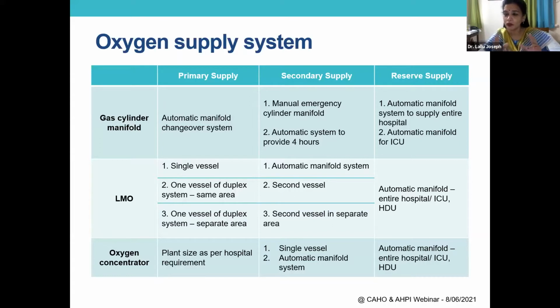Now, if you have 2 vessels, one vessel acts as a backup to the other vessel. So the second vessel is your secondary supply. And the reserve supply, again, here is an automatic manifold. Now, if there are 2 vessels in 2 separate areas, one vessel of a duplex system in one area and the second vessel in a separate area becomes your secondary supply. And then your manifold becomes your reserve supply.